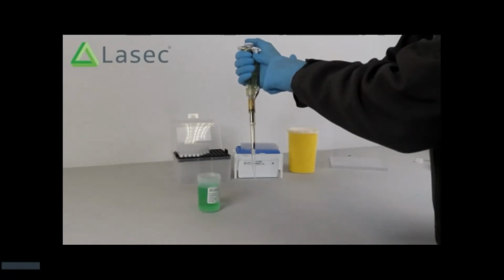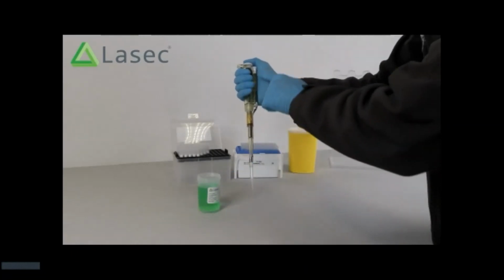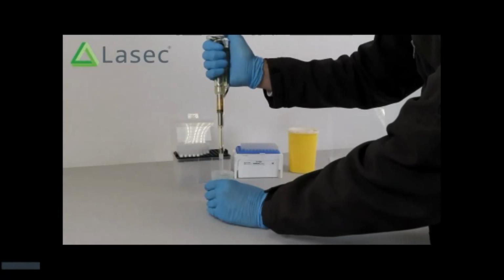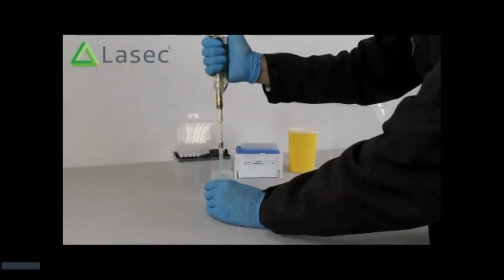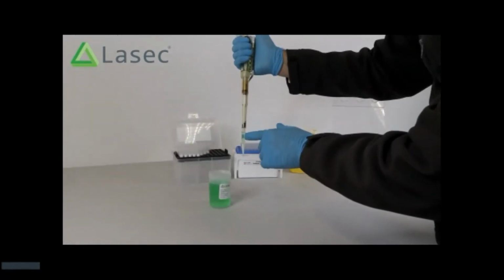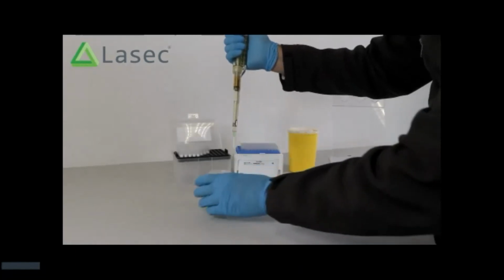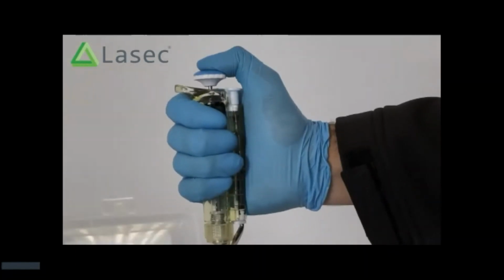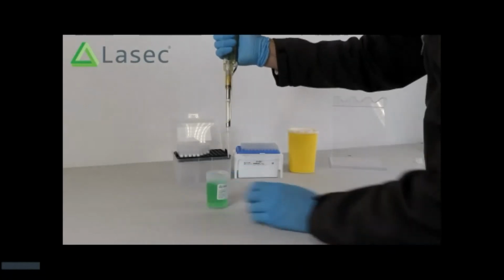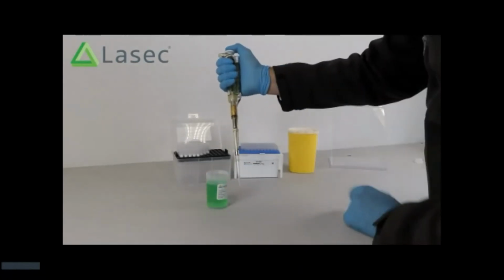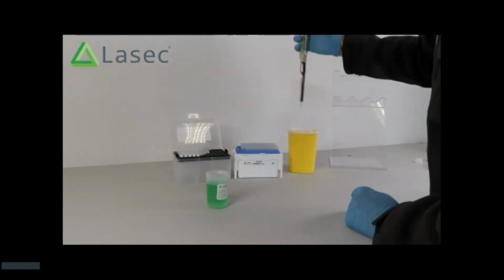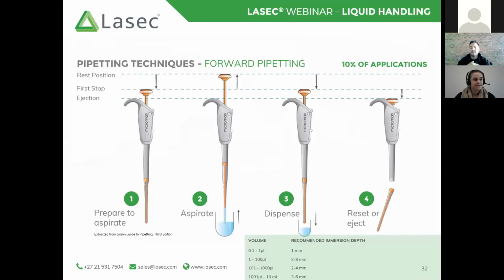In the first instance, I had a filter in that tip. What then ends up happening is that sample reaches the filter. Obviously, once any sample reaches the filter, it will be somewhat absorbed by that filter. You will lose volume, and therefore it will affect the accuracy of your results. In this latest demonstration, I decided, okay, I'm not going to use a filter tip. Maybe I'll use a standard 1000 microliter tip.